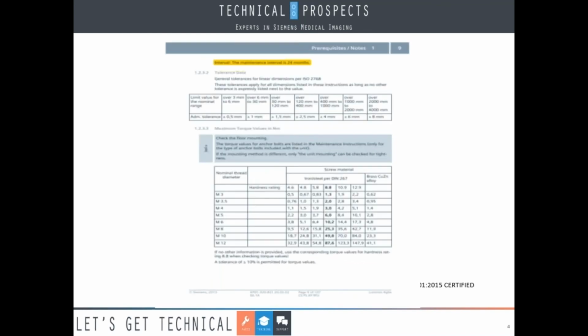Now for this one, like most X-ray fluoroscopy tables, the interval is 24 months, which is good because you basically have 16 hours if you have a full system with an overhead tube and everything. So it's good that you have 2 years to do it. Some people will come in, say in June, and say, hey, how about you take the system for 8 hours, and the operator's fine. So you just need to break it up in the right 8 hours, and then maybe you come back June next year, and they give it to you for another 8 hours. So you get the PM done in 2 years, you're good. They gave up the system for 8 hours one year, 8 hours the next, and they're pretty happy.